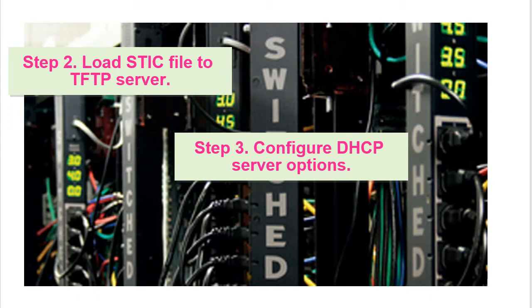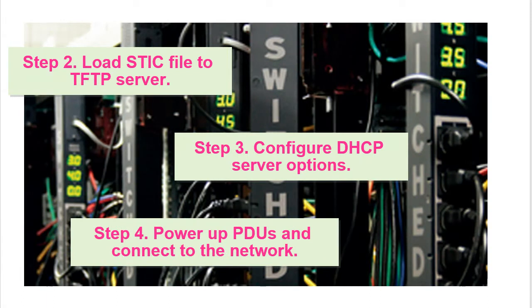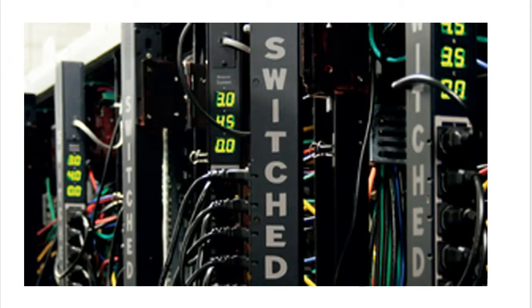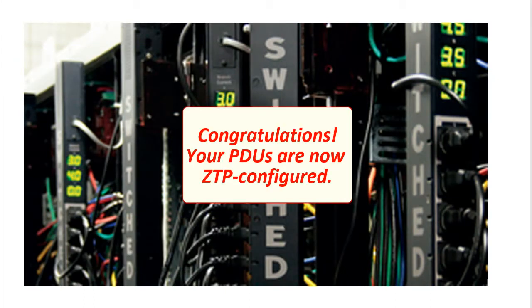Step 3: Configure the DHCP server the PDUs will use. Step 4: Power the PDUs and connect them to the network. The PDU looks for the DHCP server to get the TFTP server location, then pulls the STIC file needed to complete ZTP configuration. Your PDUs are now ZTP configured.